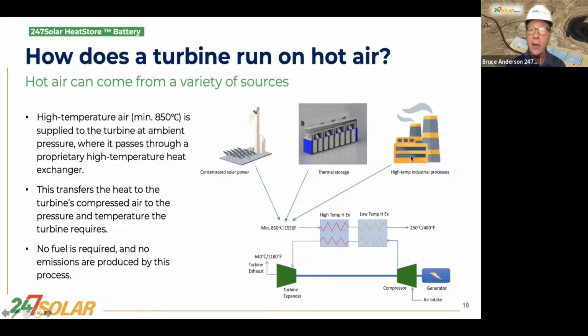So this high heat, and we're talking over 850 centigrade, goes through a heat exchanger that's in series with the turbine's already built-in low temperature heat exchanger recuperator. So the compressor compresses the air as normal, passes it through the low temperature recuperator as normal, and instead of going directly to the combustor, we remove the combustor and replace it with this high temperature heat exchanger. By the time it comes through this high temperature heat exchanger, it's at full compression and full temperature required by the turbine's expander, the turbine inlet temperature.